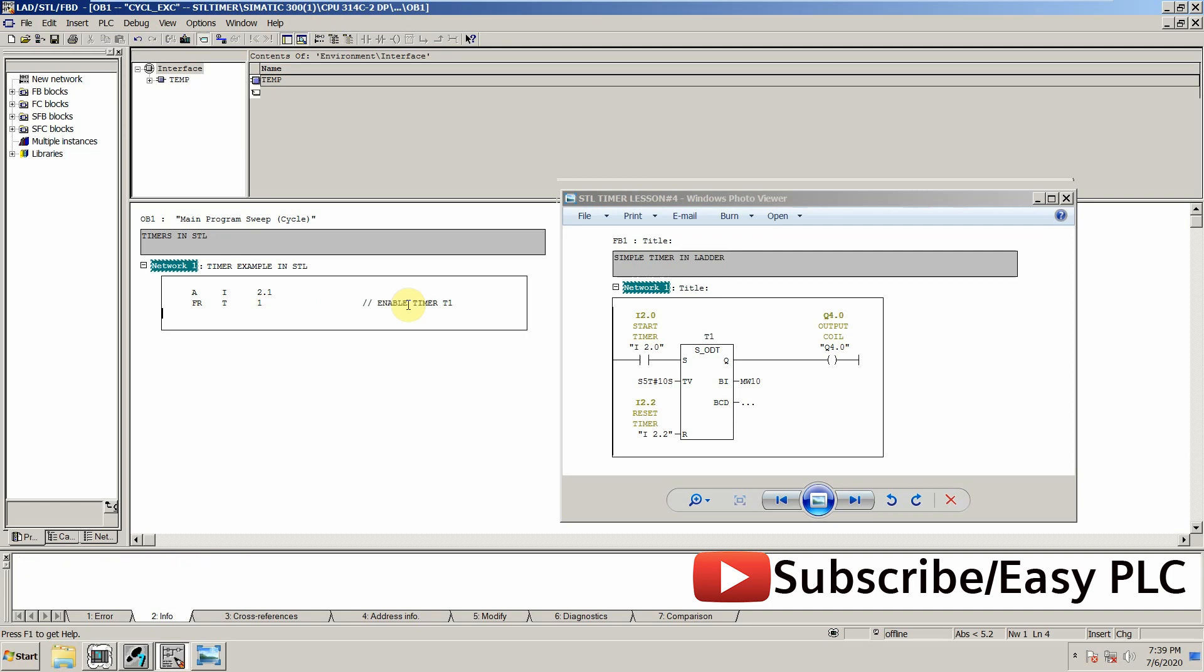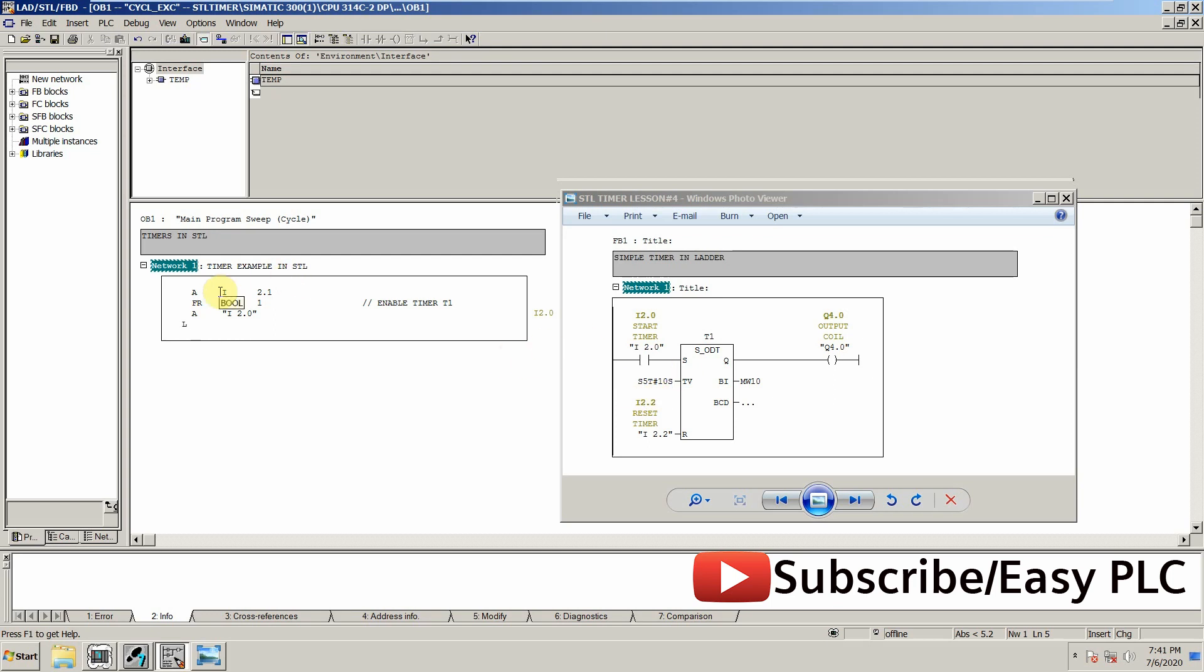The next thing is to start this timer, so we can use again AND operation. We are starting this timer by I2.0 input. We will use the load command L to load the preset value in the timer T1. Load S5T.